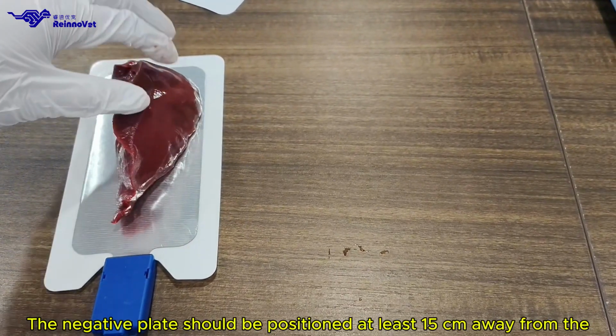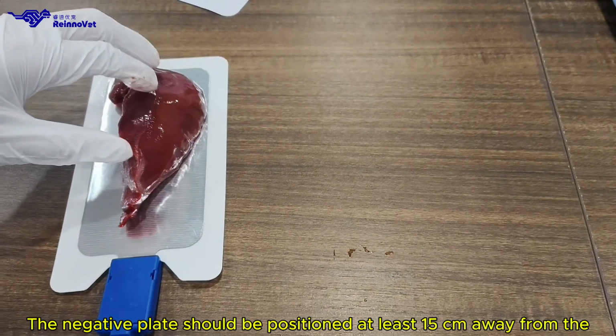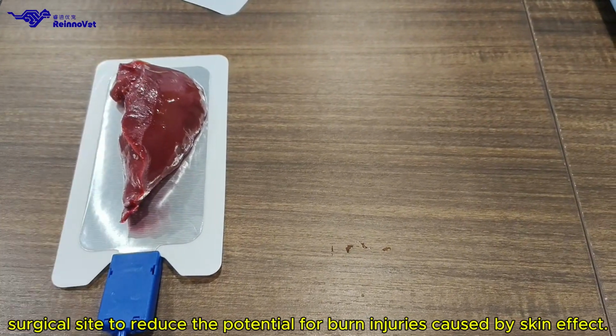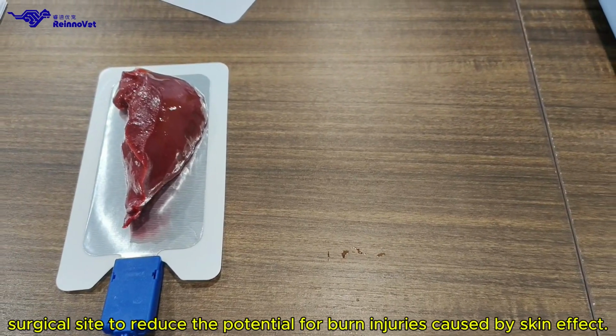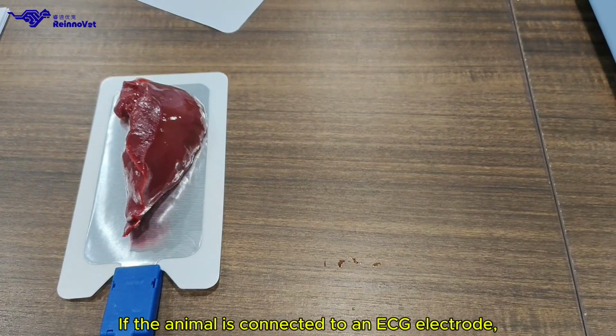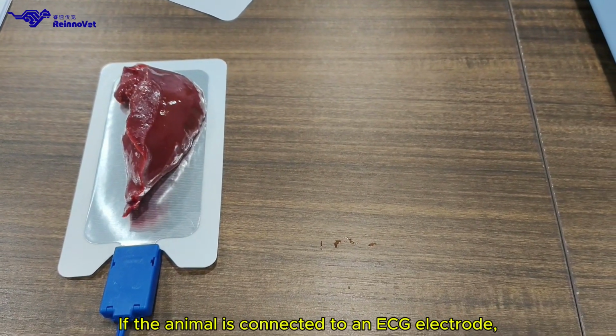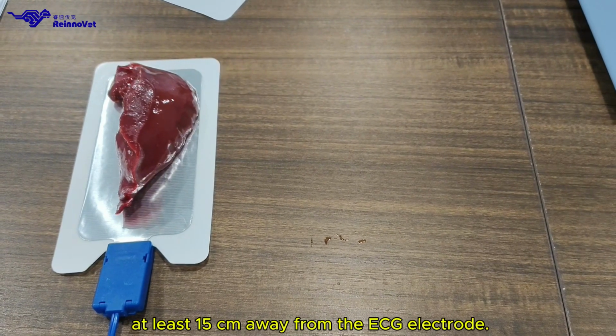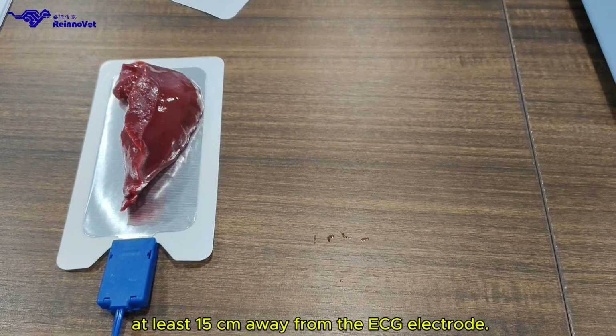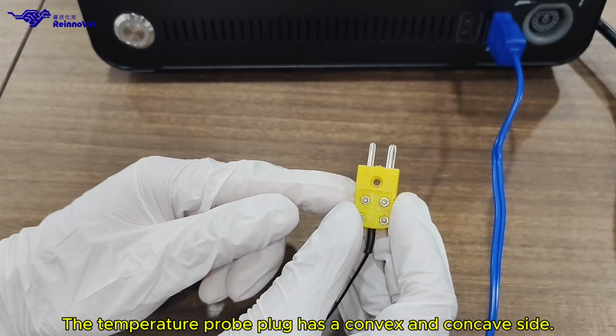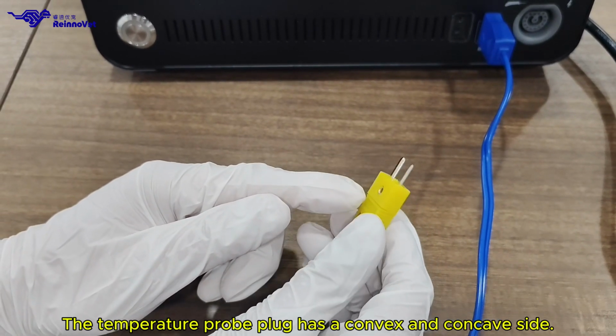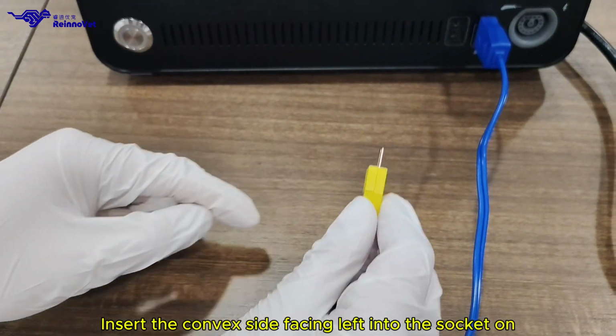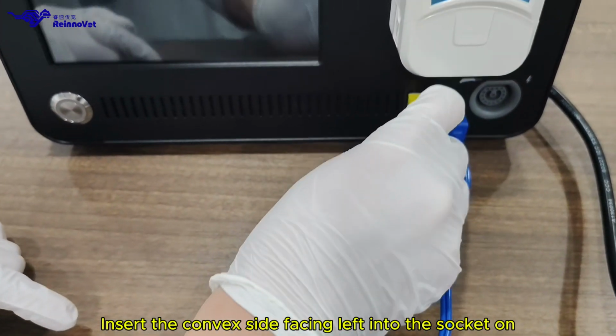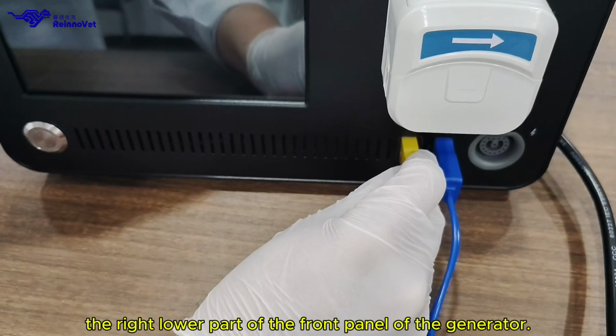The negative plate should be positioned at least 15 centimeters away from the surgical site to reduce the potential for burn injuries caused by skin effect. If the animal is connected to an ECG electrode, the negative plate should be placed at least 15 centimeters away from the ECG electrode. The temperature probe plug has a convex and concave side. Insert the convex side facing left into the socket on the right lower part of the front panel of the generator.